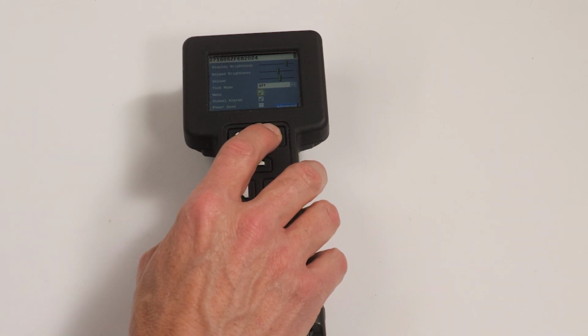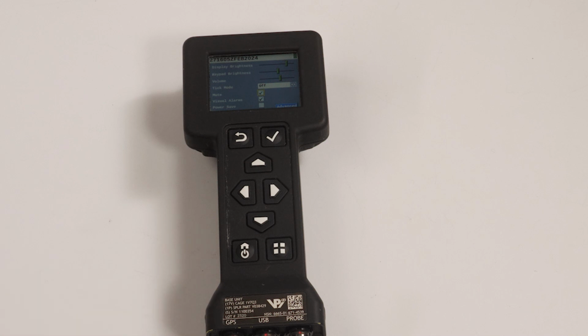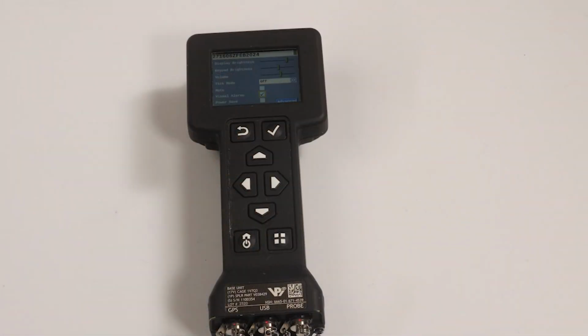Press the Enter key to activate or deactivate the mute function. Checking the mute function silences all audio, including the speaker and an attached headset. When the visual alarms function is checked, the base unit will display a visual alarm anytime the base unit measures radiation above the alarm threshold, detects a fault during built-in testing, or detects a notification during built-in testing.